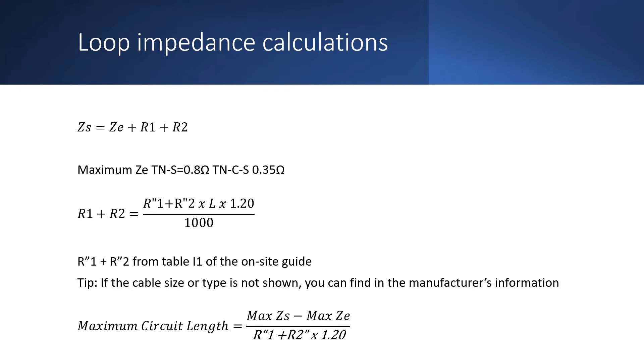So we know what to use for ZE, we now need to know what to use for R1 plus R2. This can be calculated by using the values in table I1 of the on-site guide. The table provides tabulated values quoted in milli-ohms per metre for a variety of sizes of line conductor and CPC. These figures are multiplied by the length and a correction factor of 1.2 and then divided by 1000 as shown in the example here.